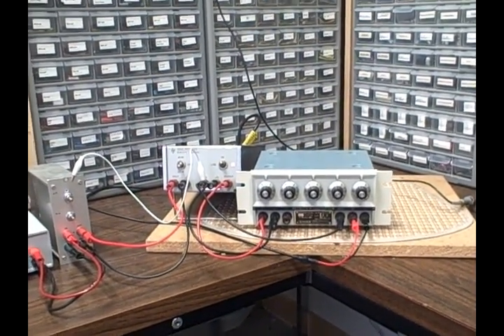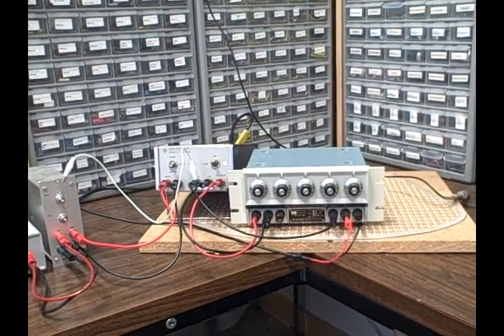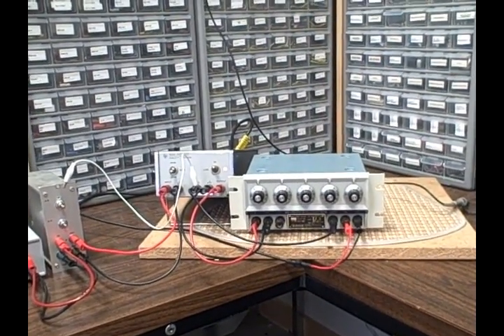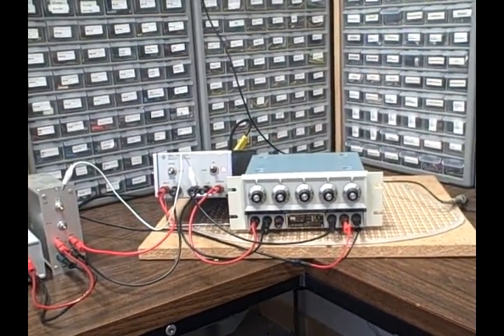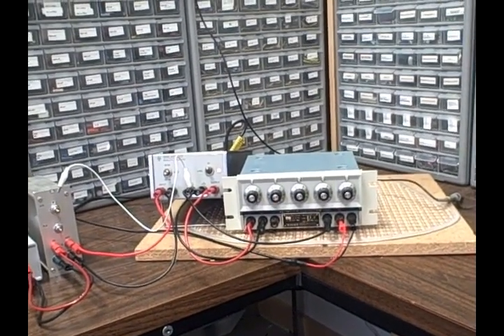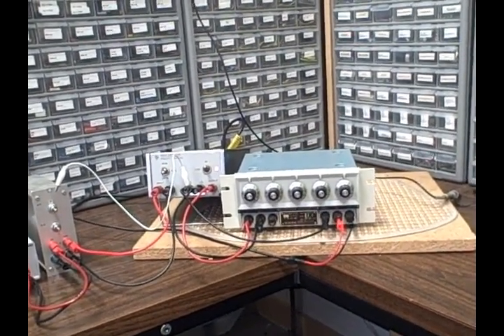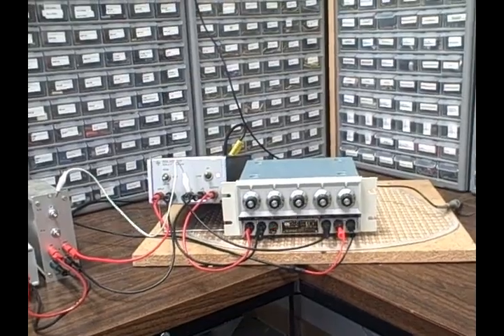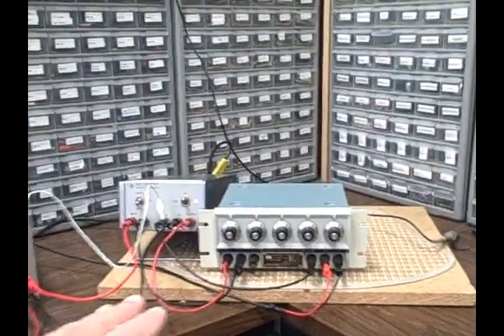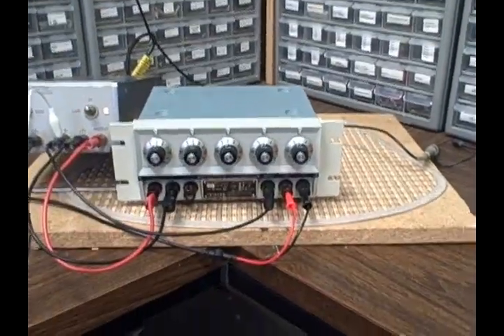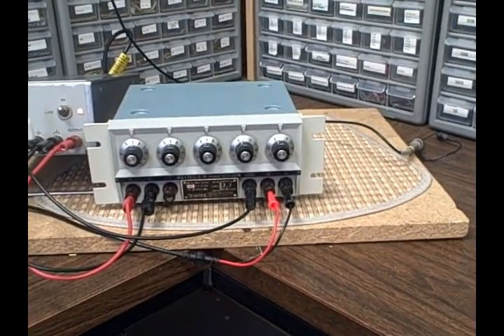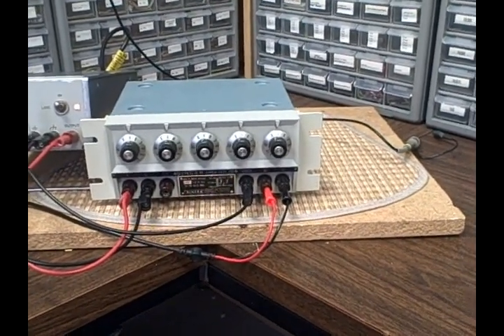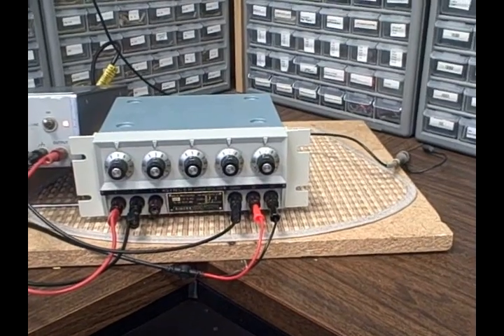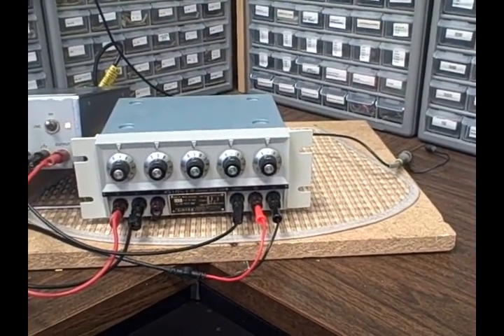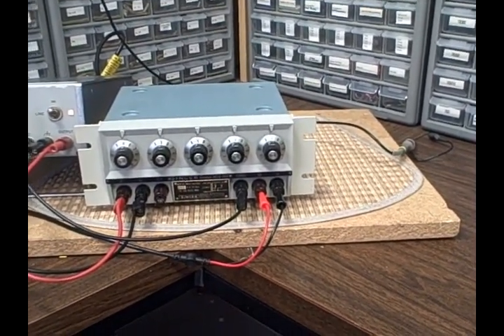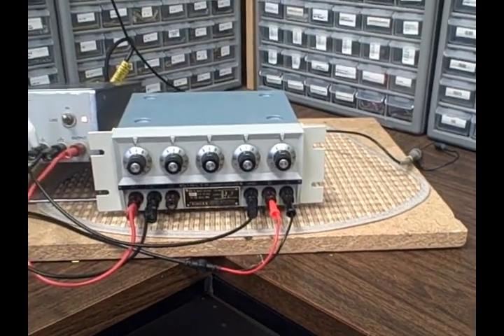Ratio transformers are special toroidally tapped transformers. They're tapped at 10 positions generally. And in this particular unit right here, which is a Gertsch ratio transformer, but it was apparently licensed under Singer, there are five transformers inside of there, each tapped at 10 positions.